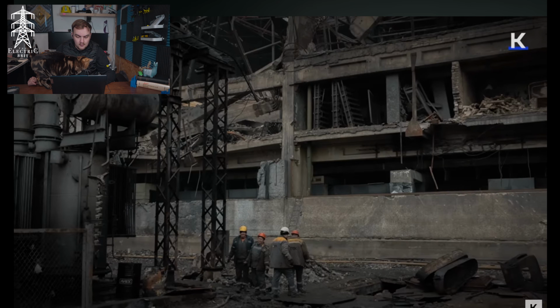So yeah, taking a look at this transformer on the left of the screen, that looks like a slightly smaller transformer if I had to guess. So probably not the 330 kV, which is closer to the 400 kV, in between 275 and 400 in the UK. And on the lower side we use 132, which is the bottom of transmission but the top of distribution in the UK, because we separated out at that level. So that looks like a 132, or in their case a 110 kV transformer.